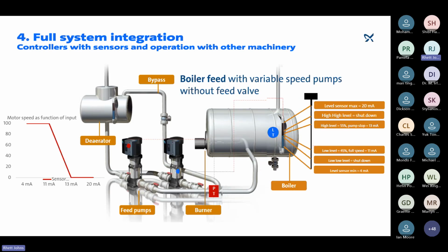So looking then at what we would want to do in a system like this, the first step is we want to go away from that modulating valve. We want to move towards direct level control based off of the needs of the boiler, and that's fed back direct into speed control on your pumps. So the level transmitter is fed directly back into your pumps, or otherwise indirectly through the controller on the boiler, and that is then used to regulate the speed at which your pumps are running.